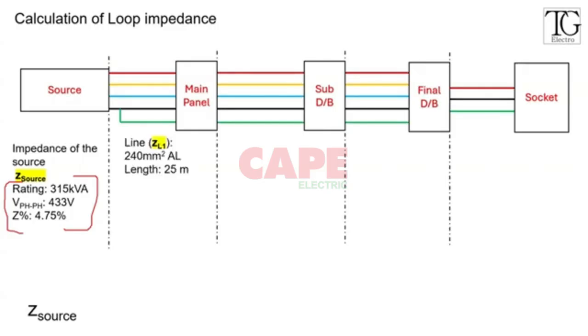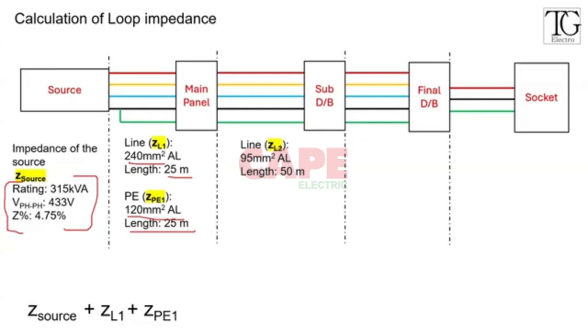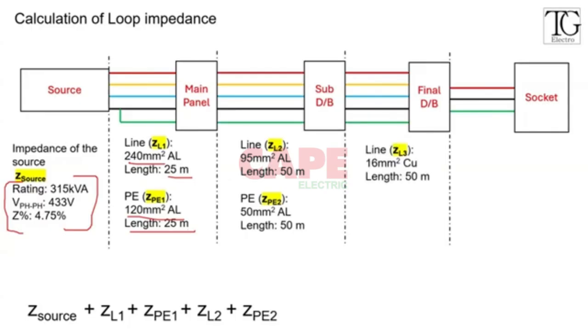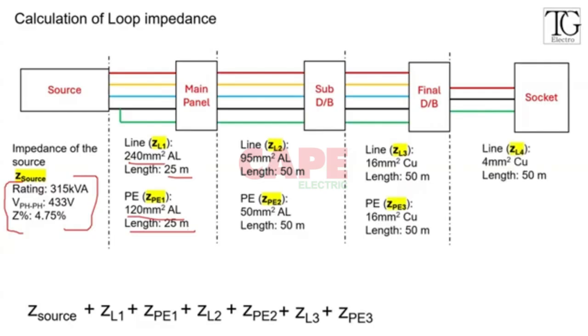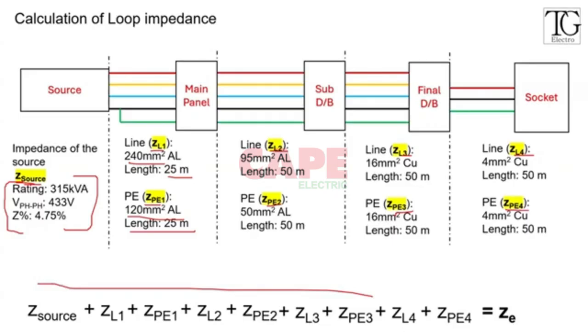So first you have to add that. With the line conductor, I'm putting a 240 square mm conductor, length 25 meters. The PE conductor is also an aluminum conductor. I've considered aluminum. In the sub DB, it is 95 square mm, and the PE conductor of the sub DB is 50 square mm, 50 meters. And this is 16 square mm copper, 50 meters. Here also I'm putting the same size of PE conductor, 16 square mm copper, 50 meters. Then to the socket it is 4 square mm copper, 50 meters, plus 4 square mm copper, 50 meters. When you add all these, Z source, ZL1, ZPE1, ZL2, ZPE2 and so on, into this expression, you get this ZE value. So this is how to make it.